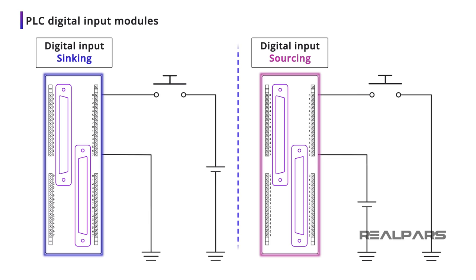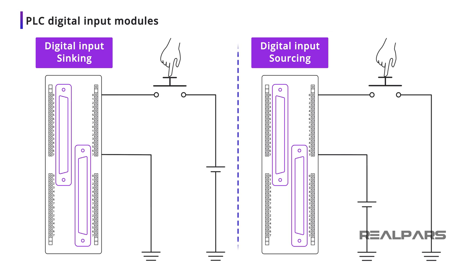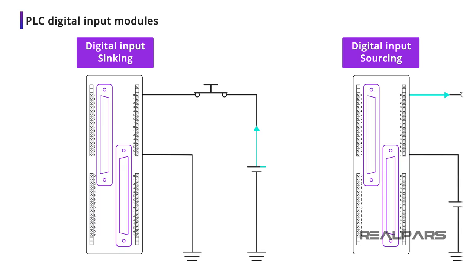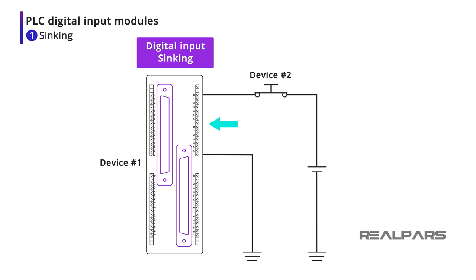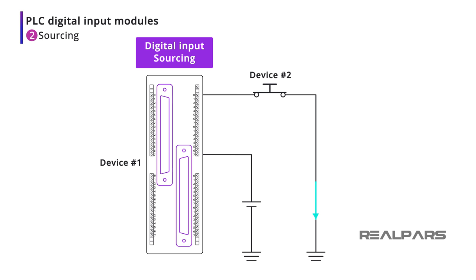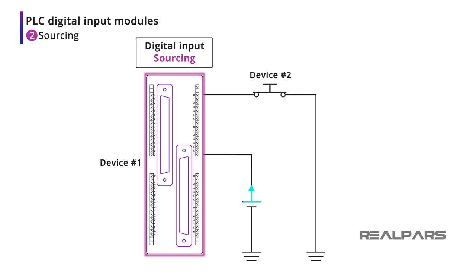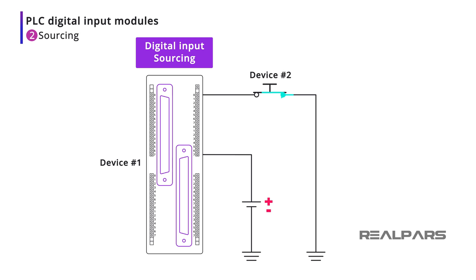PLC vendors manufacture both sinking and sourcing digital input modules. Let's explore what they are and how they differ. Remember, it's all about the direction of conventional current flow. Let's have a look at two devices with current flowing between them — one device is a PLC input module and the second device is a push-button switch. Based on the connection polarity, the sinking module will have the current flowing into it from the switch. Now, if our PLC input module is a sourcing module, based on the connection polarity, the sourcing module will have the current flowing out of it.